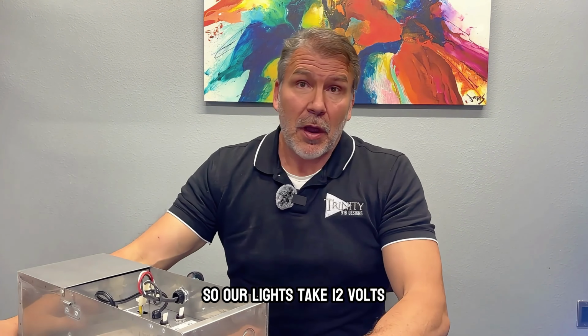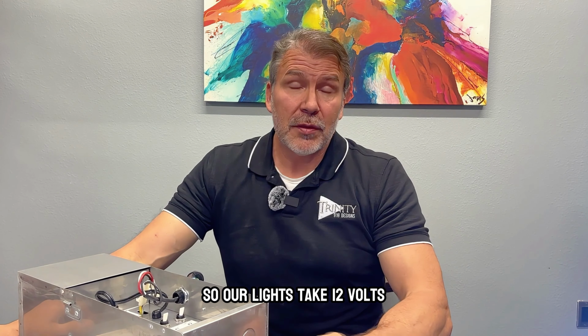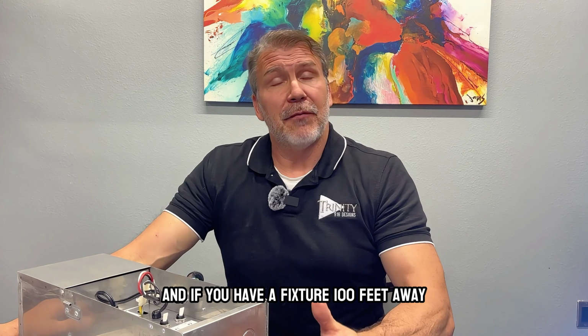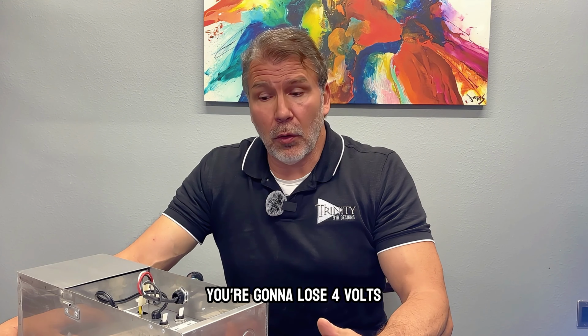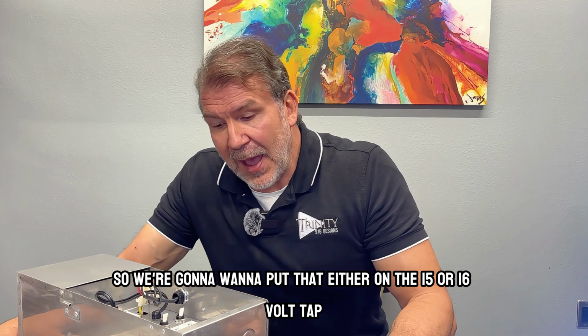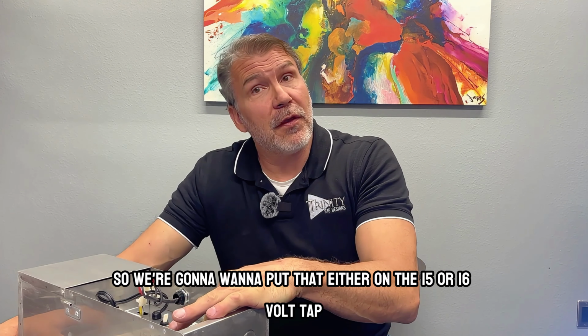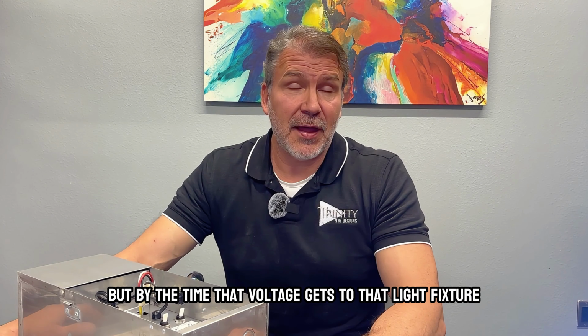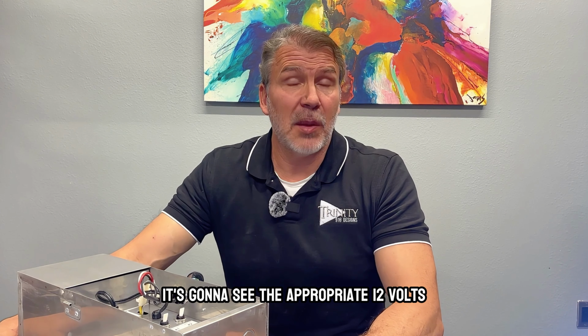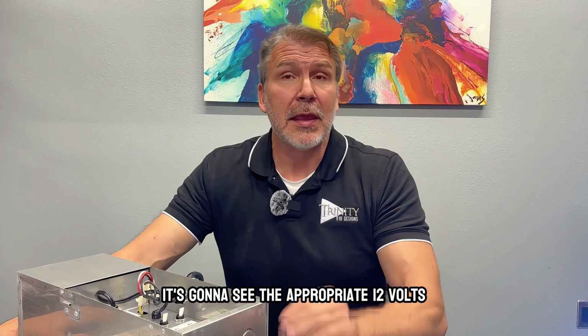Our lights take 12 volts. If you have a fixture 100 feet away, you're going to lose 4 volts. So we're going to want to put that on either the 15 or 16 volt tap, so it puts out 16 volts, but by the time that voltage gets to that light fixture, it's going to see the appropriate 12 volts, and it will be just as bright as all the rest of them.